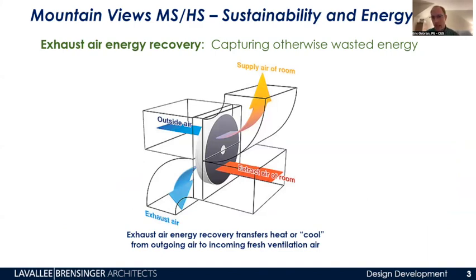The other technology is energy recovery. People are often surprised how much energy it takes to ventilate a school or any building with a high ventilation load. Fresh outer air comes into the building and stale exhaust air goes out, and both air streams run through a slowly rotating wheel. This doesn't let the air streams mix, so fresh air stays fresh and stale air stays stale, but the wheel allows heat transfer. Warm air leaving the building warms the wheel, which rotates and passes that heat to the cold air coming in during winter. This can save 70 to 80% of heating from one technology that uses very little energy, and we're using it for all ventilation and exhaust in the entire school, saving a big chunk of energy.